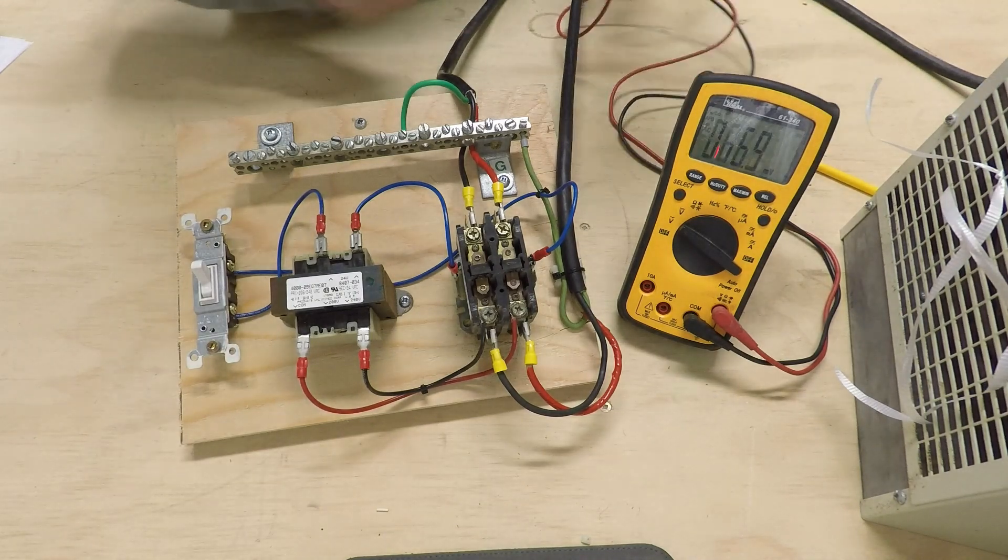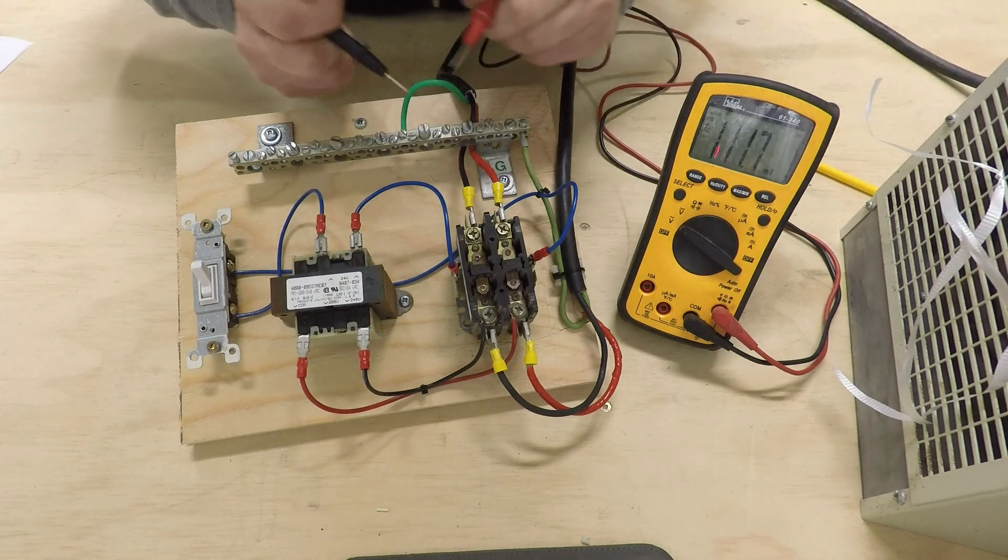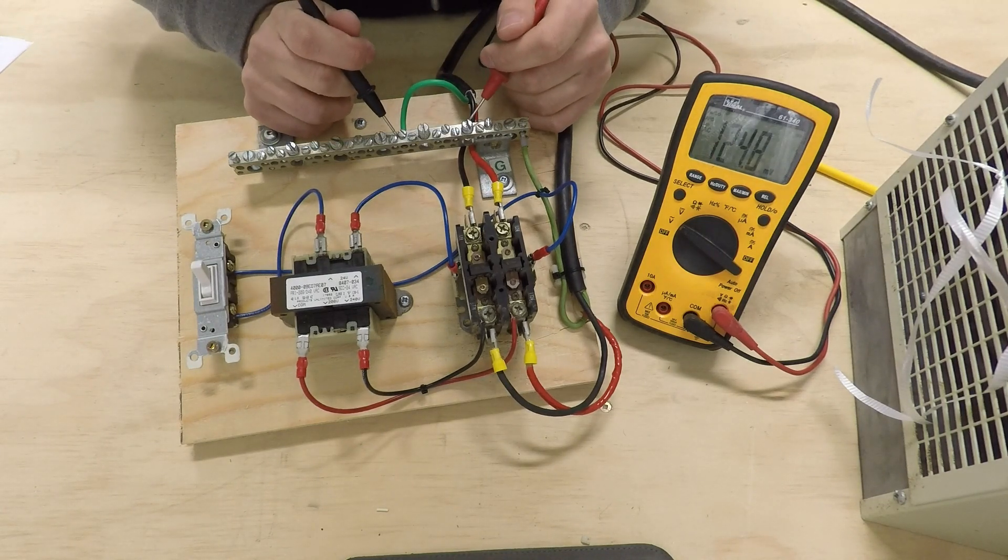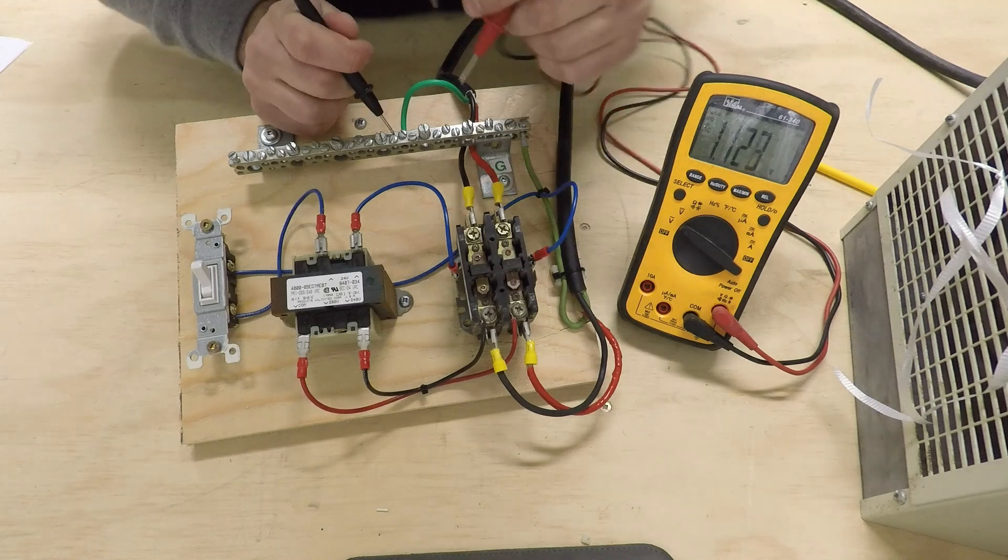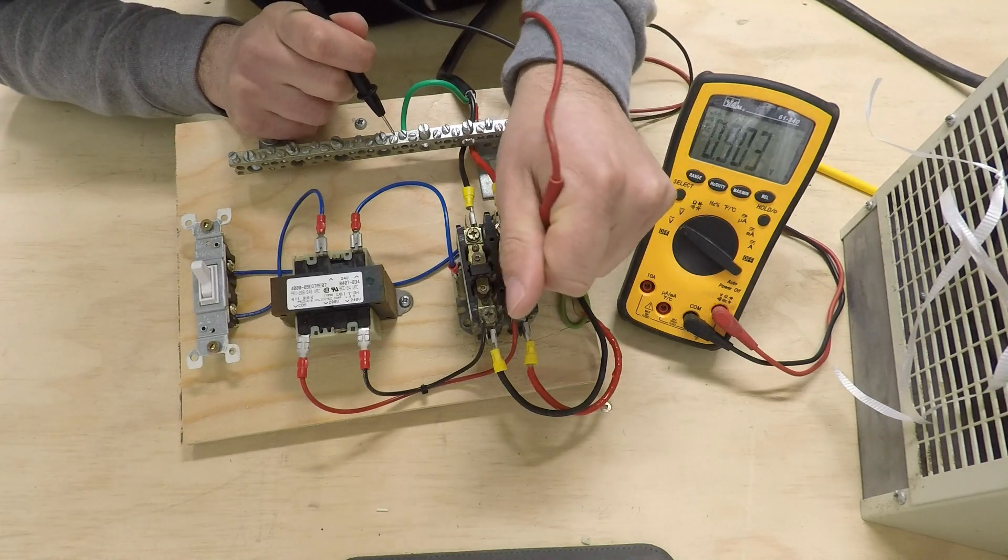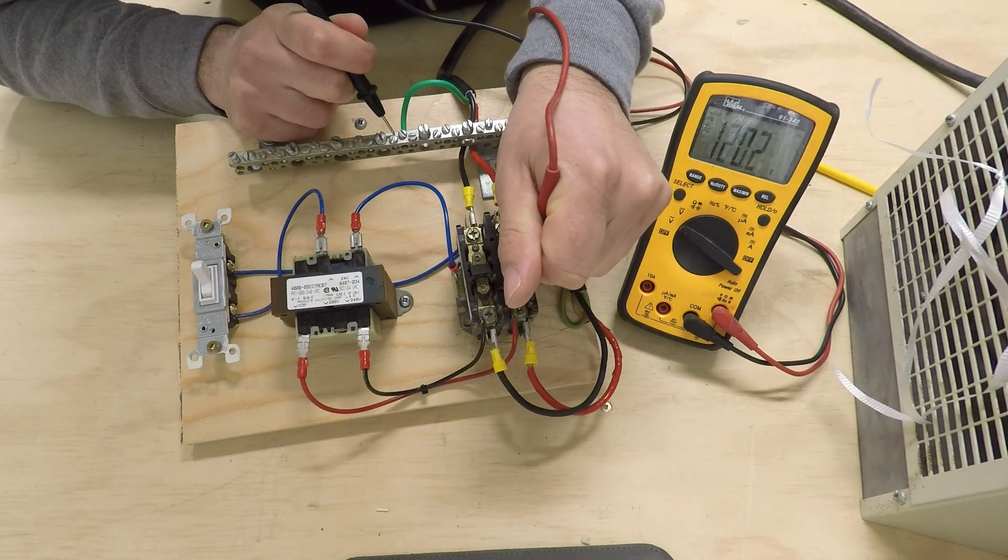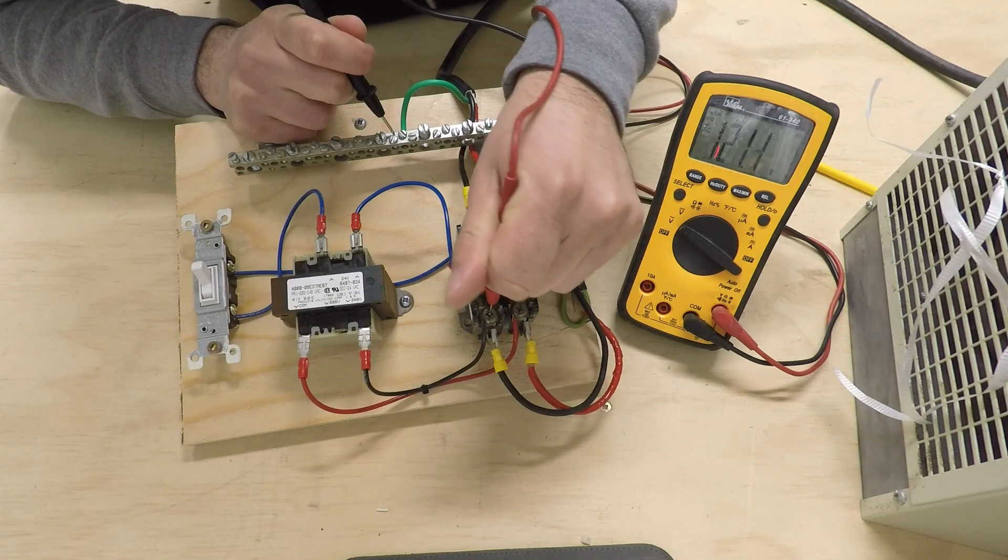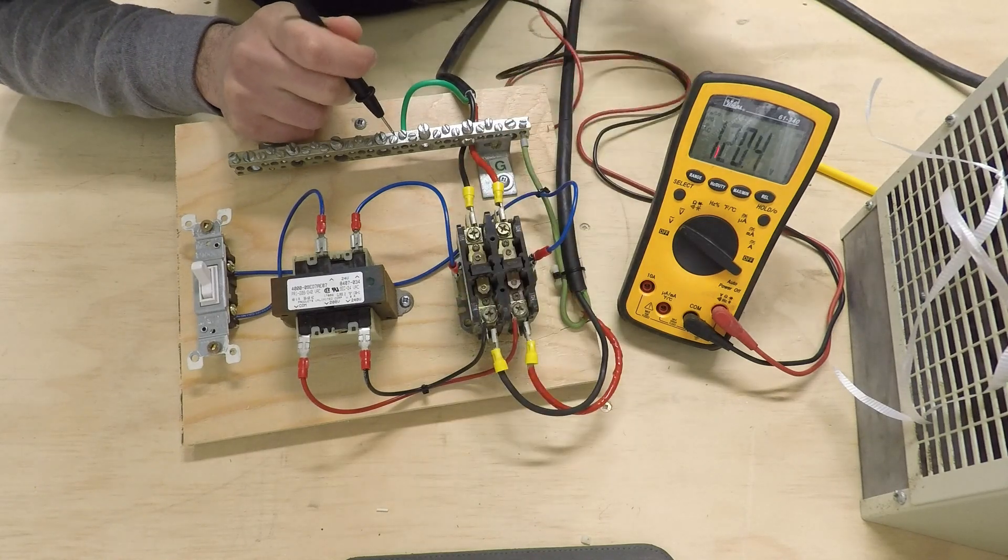So you're going to take a couple of measurements here. And I'm going to show you where people sometimes get a little bit confused with this measurement because it's kind of misleading. So coming in, I've got approximately 120 and on my other phase, I've got 120. That's where you get your 240.